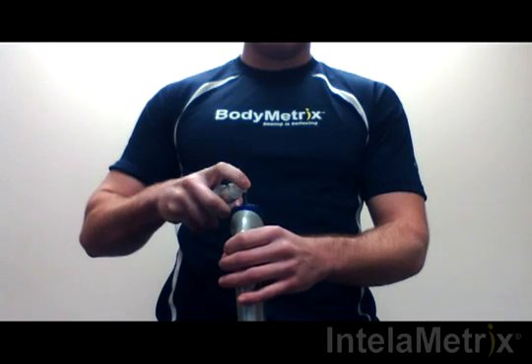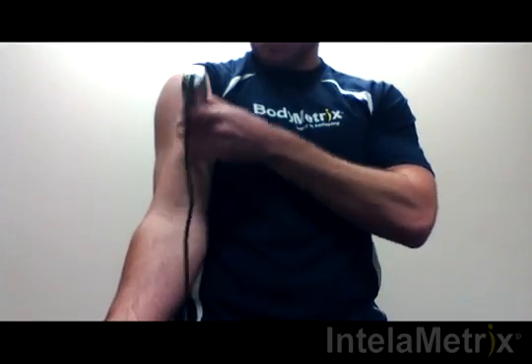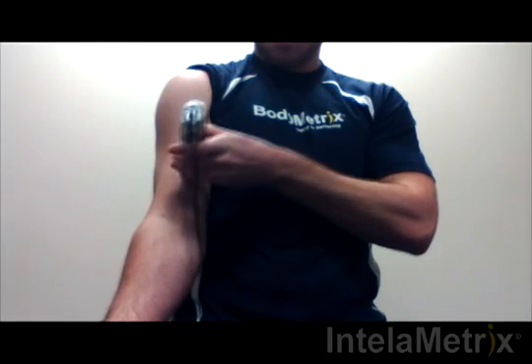The measurement technique will now be demonstrated. Before taking your measurement, place a small amount of ultrasound gel on the front face of the device. Next, take the BodyMetrix ultrasound device and place the face on the bicep's measurement site and spread the gel within the optimal area. After the gel has been applied, you are ready to take the measurement.